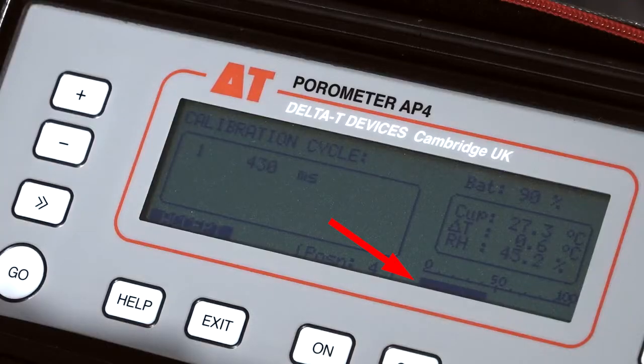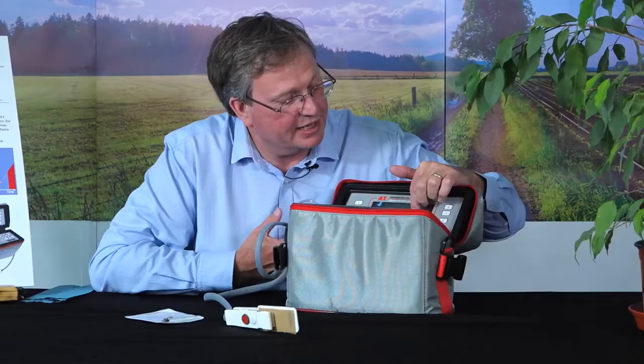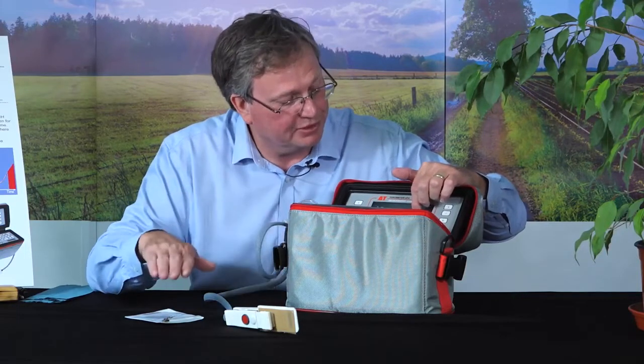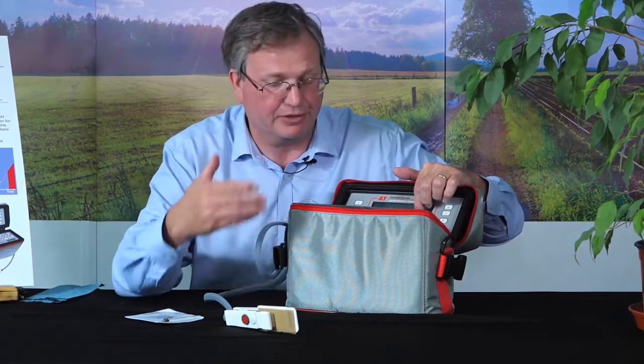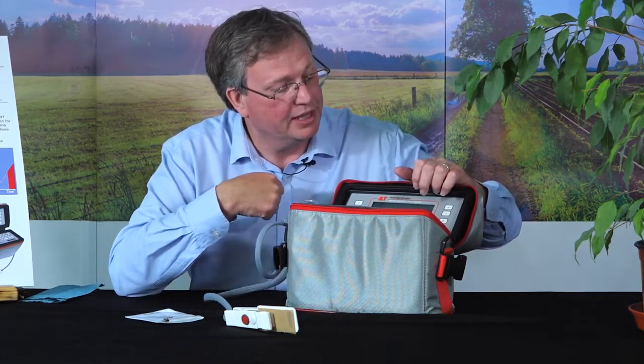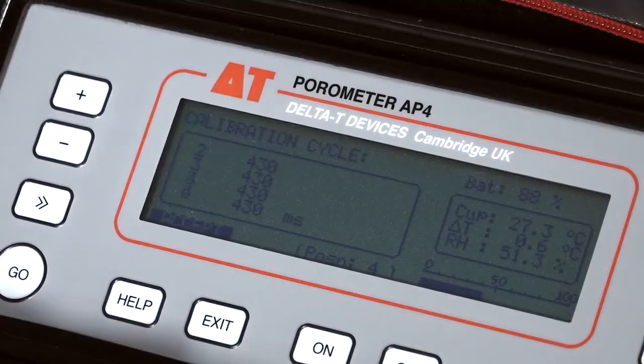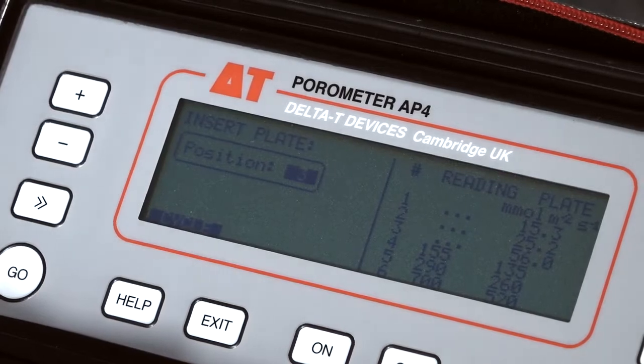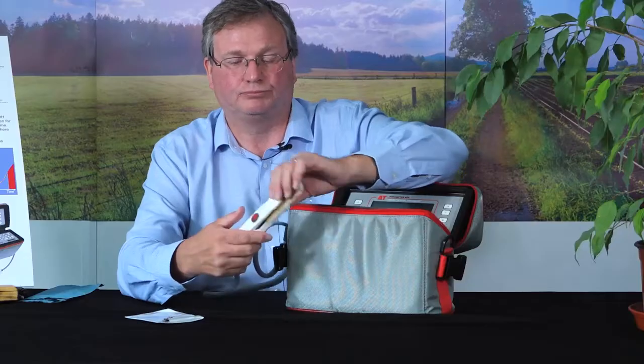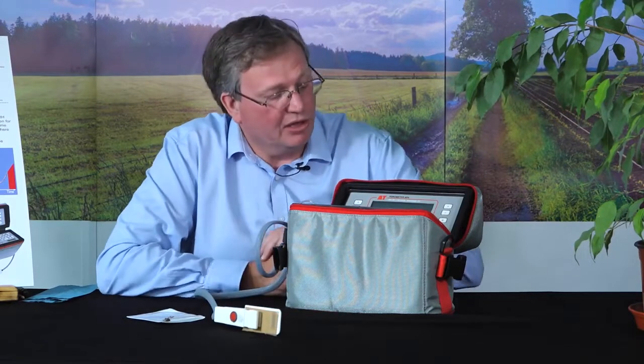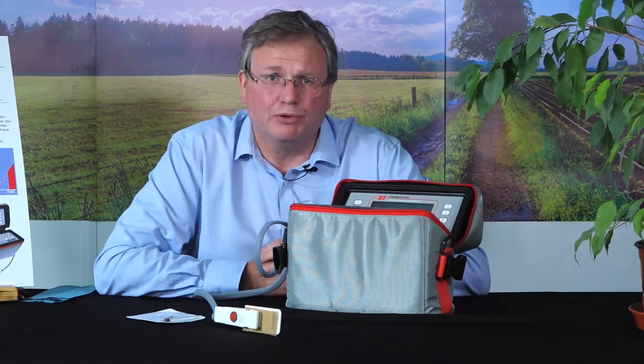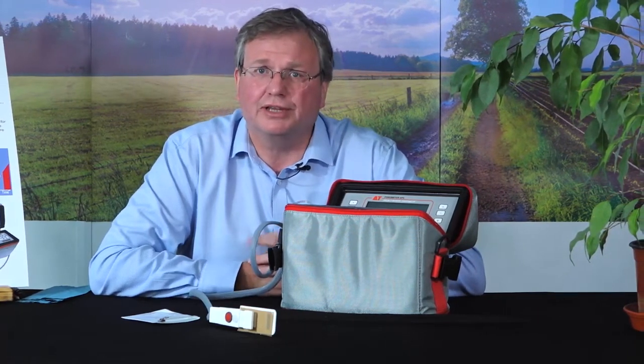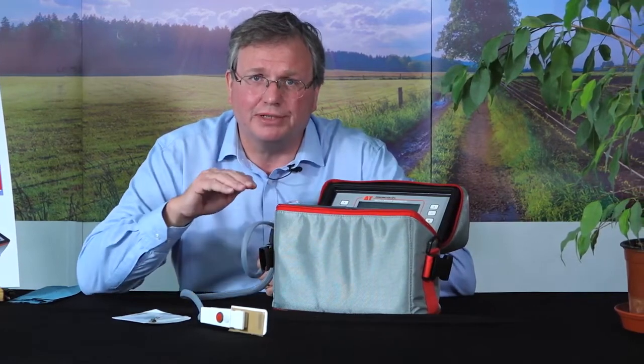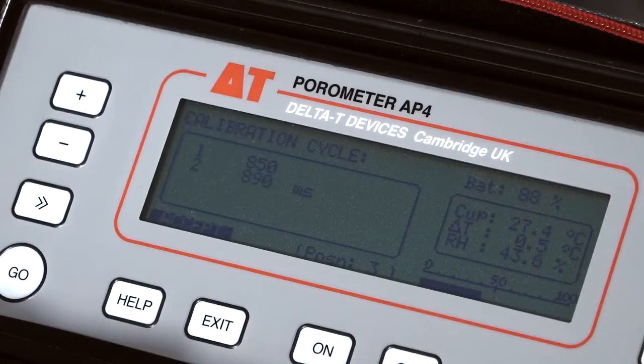You might be able to see the black bar on the screen here moving as the humidity increases and then falling back rapidly as the pump activates, as the humidity drops because of the dry air and then rises again because of the wet filter paper creating our humidity. We have got the double beep, so we can accept that value and move on to position 3. This should take a little bit longer now because the holes at position 3 are much smaller. So it's going to take longer for that humidity to increase in the cup, to go from the ambient to 2.3% above ambient. We've achieved the double beep, which means we have a stable reading.